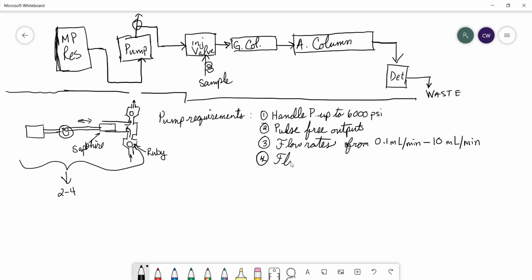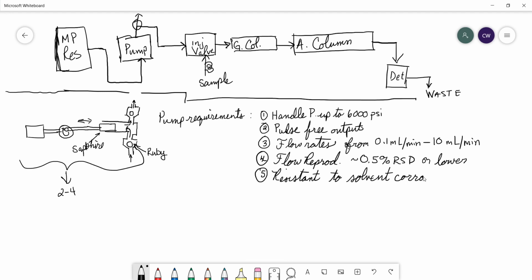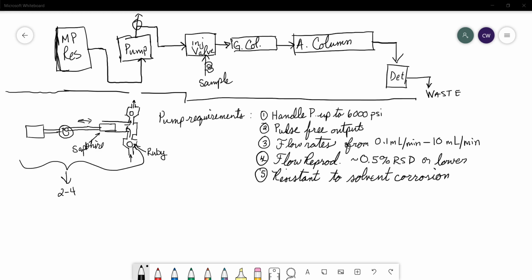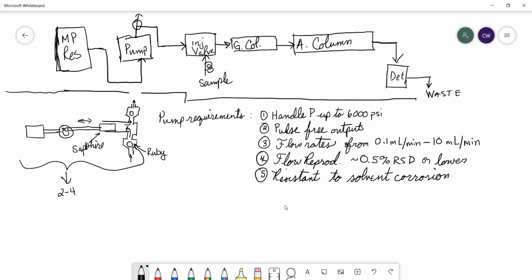Because their flow reproducibility has to have a 0.5% RSD or lower. So when we program in a flow rate to the pump, we want it to be able to give it to us from start to finish with very little fluctuation. And then finally, it must be resistant to solvent corrosion. So those are our 5 key characteristics of a pump.